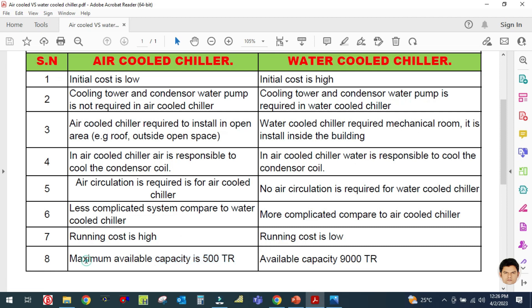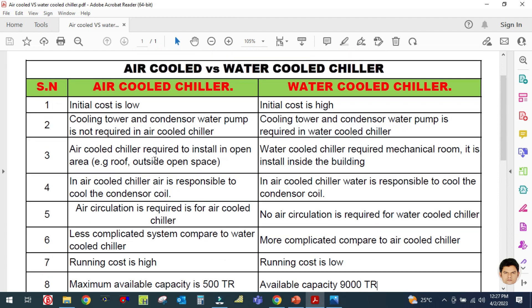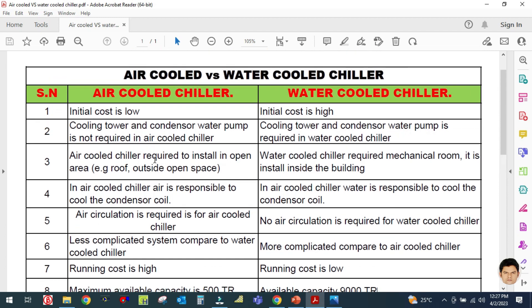The last difference is the maximum available capacity. For an air cooled chiller, the maximum available capacity is 500 TR (500 tons), while a water cooled chiller is available up to 9000 TR. This is why the water cooled chiller is used for bigger systems and bigger projects, while the air cooled chiller is used for smaller projects.